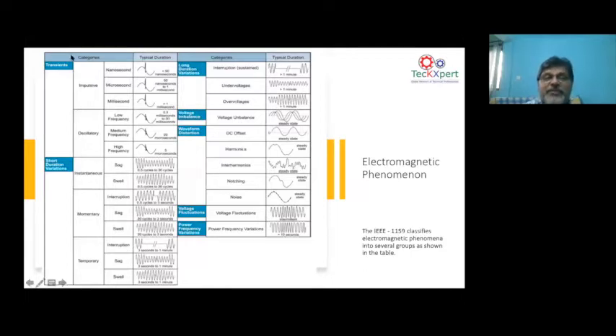Now, the other one which you can categorize is oscillatory. This is another type of transient. And where does an oscillatory transient come from? Everybody will be familiar with capacitor bank switching. If you look into a capacitor bank installed in the utility, like in TNEB or KEB or whichever state you come from, the substations install capacitor banks. And what is the purpose of the capacitor bank? They install this to improve the voltage in the network, and they bring in this capacitor bank manually. They switch the capacitor bank in and out so that the network distribution voltage is maintained at the level that is required.